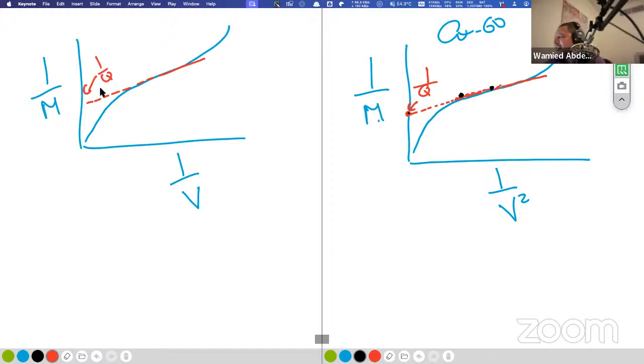The general recombination, just to give you a brief idea, in continuous beam, it varies as 1 over V squared. In pulse beam, it is 1 over V. So that's why we get these scales. There is some fundamental physics actually behind this.